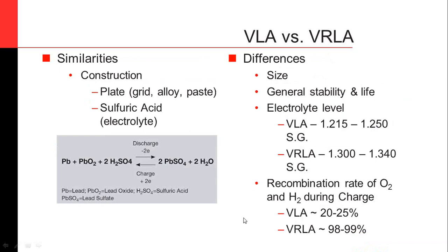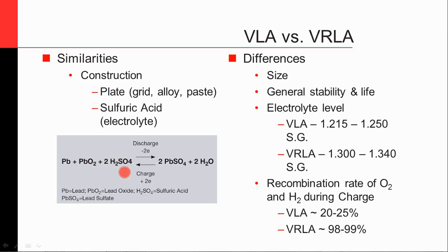Some similarities and differences: these are not necessarily all similarities or differences, nor is this intended to indicate what specific battery you need for your application. Both have similar construction with the plates being a grid base of some sort of lead alloy and a paste material. Both use sulfuric acid — lead is the negative plate, lead oxide is the positive plate. In the charged state you have sulfuric acid; in the discharge state both plates become lead sulfate and you get water.